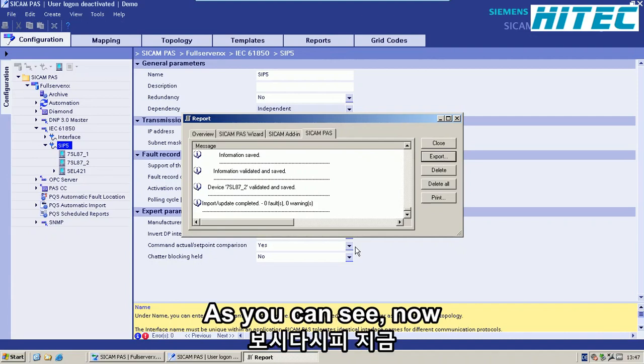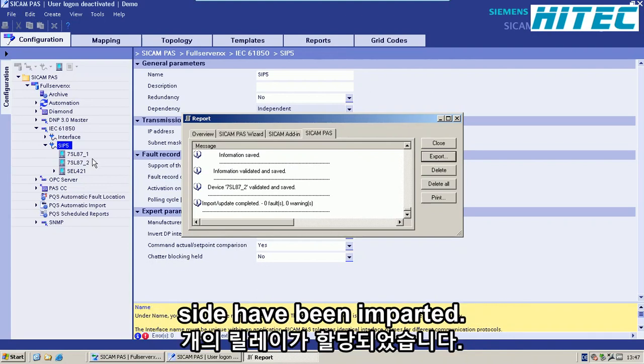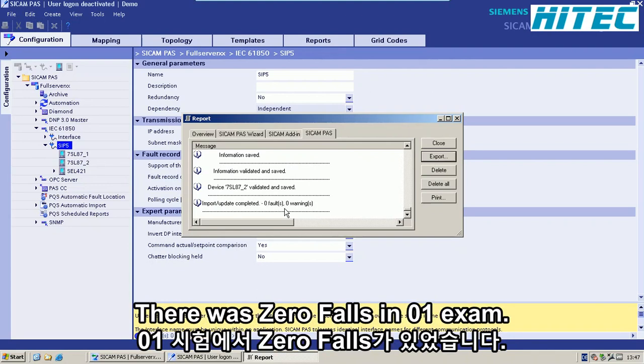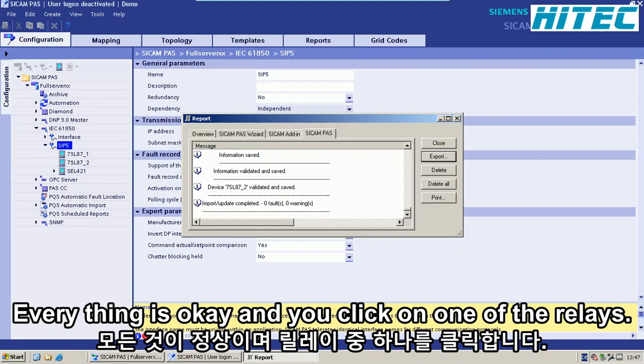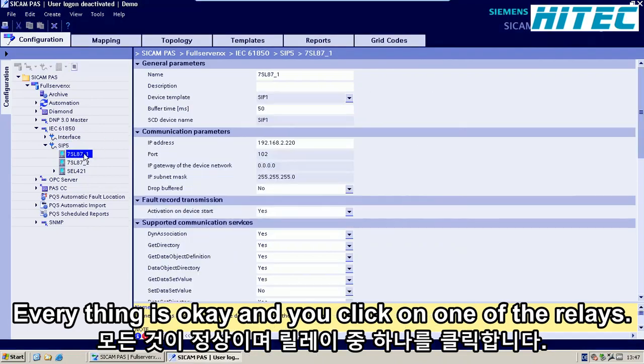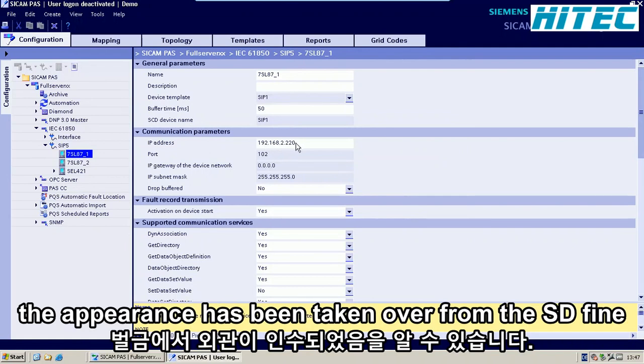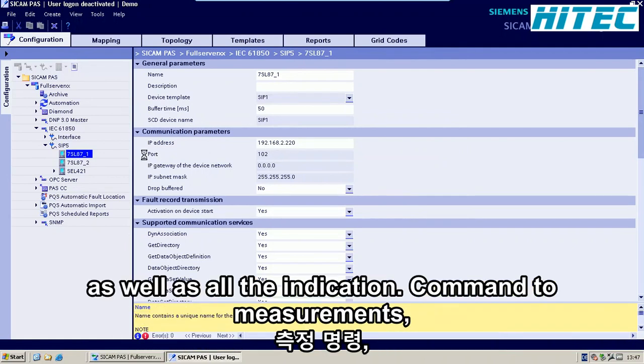As you can see now, the two relays on the left-hand side have been imported. There were zero faults and zero warnings — everything is OK. If you click on one of the relays, you can see that the IP address has been taken over from the SCD file, as well as all the indications, commands, and measurements.